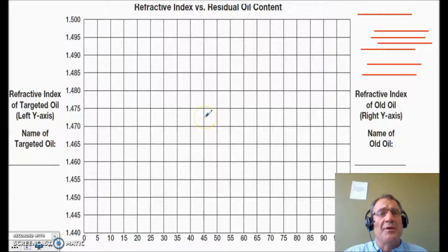Good morning, everyone. My name is Greg DeBorn, and today we're going to learn how to use the refractive index chart to prove that we've got the oil change to the point where we have less than 5% residual of the original oil in the system.